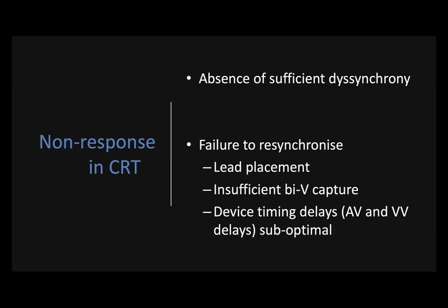Some of the elements involved in this require changing the atrioventricular delay, the time when the atrial signal captures the atria, and the time when both ventricles are resynchronized. That's the atrioventricular delay. Devices now have the technological competence and software to support changing the AV delays from 0 as far as 350 milliseconds in order to find the sweetest spot that improves filling of the ventricle.